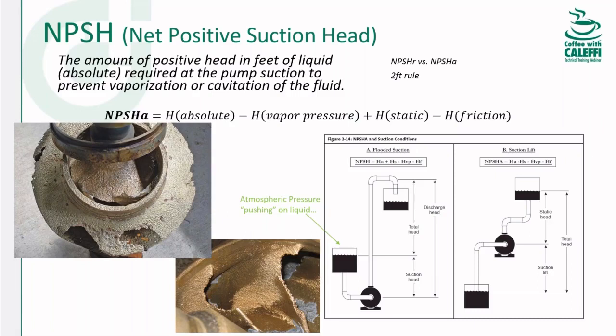I see a lot of you are running away from your computers. Come back. It's not that complicated, but you got to understand the basics. So the definition: the amount of positive head in feet of liquid, absolute, required at the pump suction to prevent vaporization or cavitation of the fluid. So in layman's terms, the impeller is pulling the water into the eye, and if it pulls too hard, the pressure drops low enough so that the water flashes to steam.